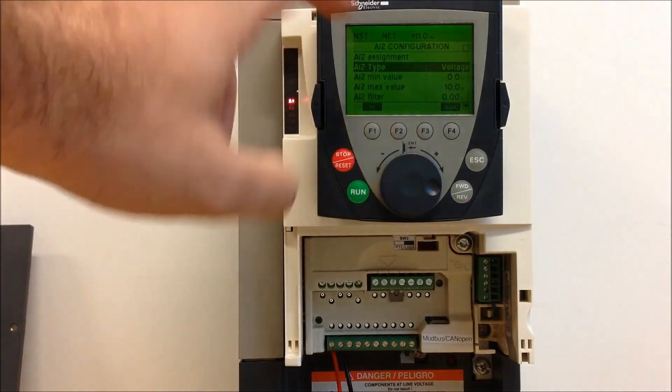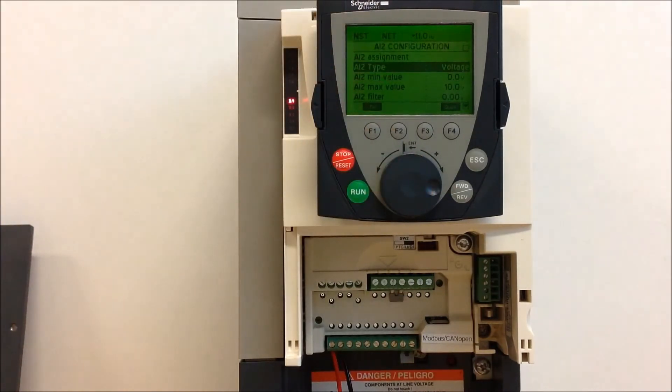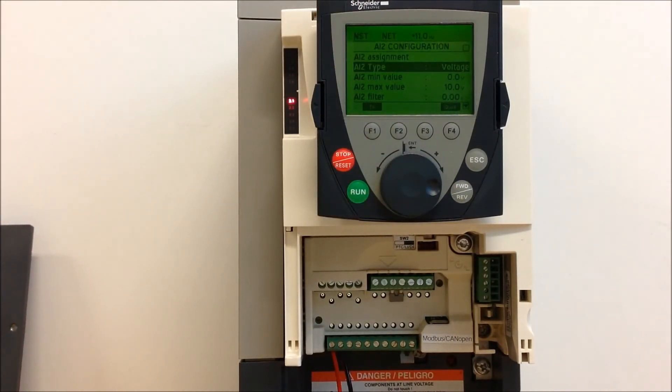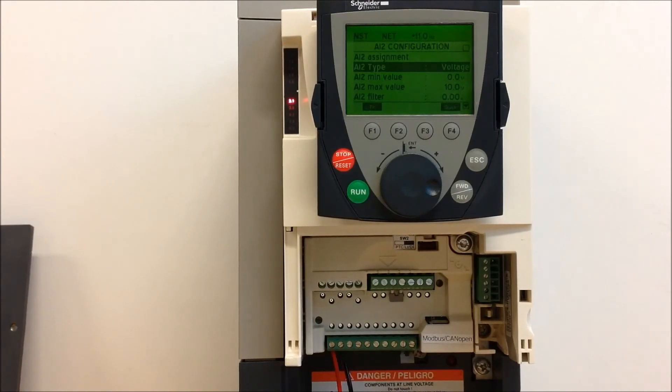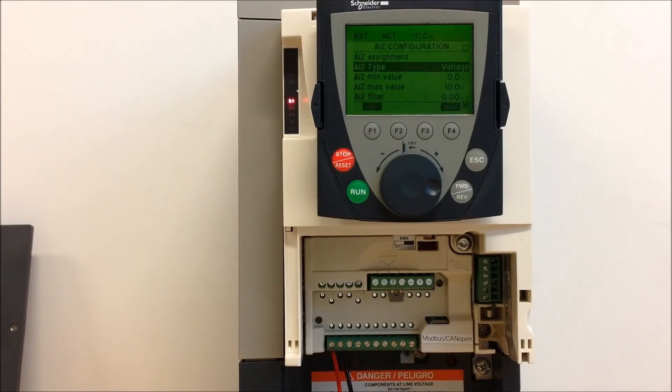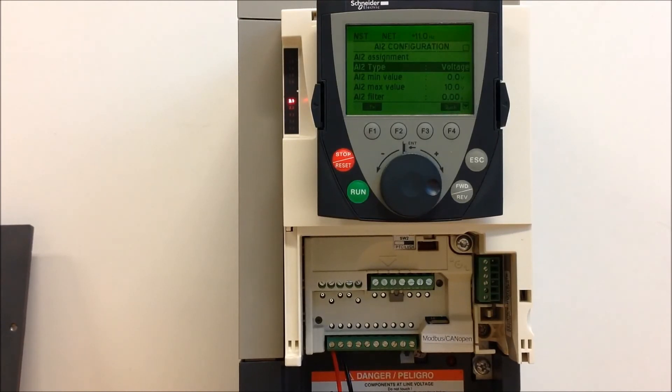And now you'll see that your minimum and maximum is 0 to 10 volt DC range. This is how you basically set your drive to accept a 0 to 10 volt DC on AI2 instead of a 4 to 20 milliamps on the ATV61 and ATV71 drives.